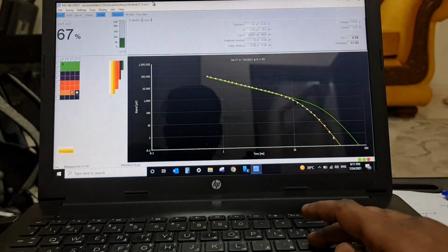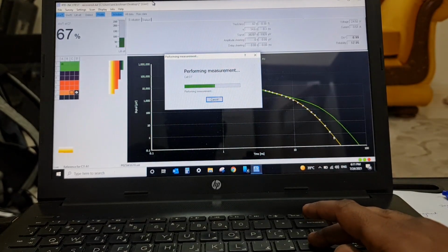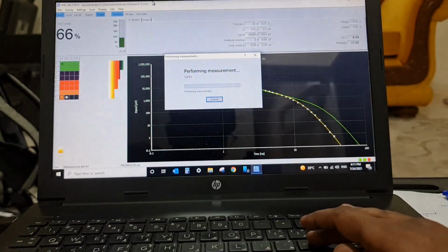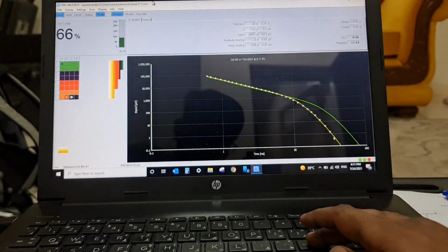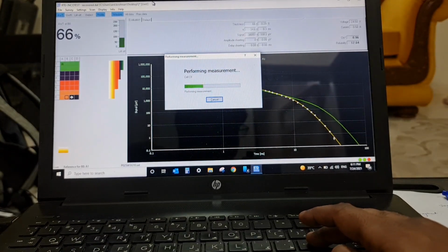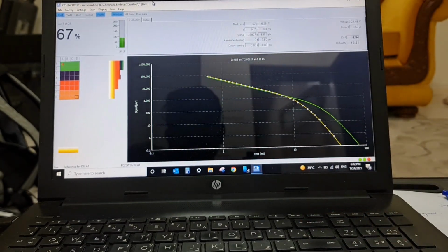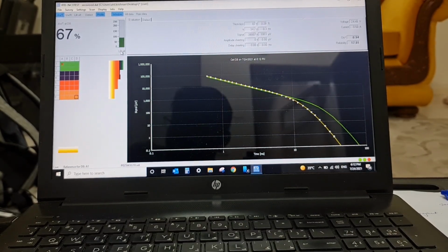So actually it is very fast. In EncoTest, data acquisition is very fast. Once the grids are selected, then we can directly press enter to get the details, means acquire the data. So all the 32 cell readings are taken.